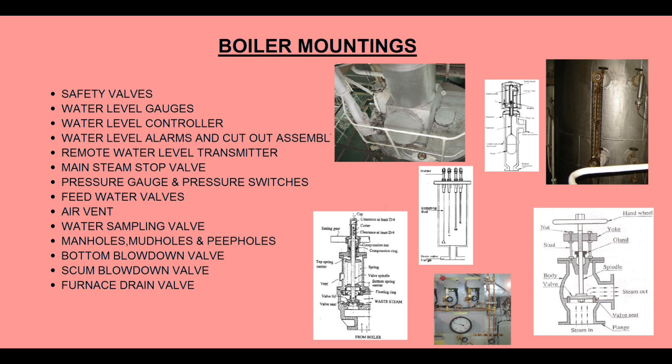Scum valves are fitted to the steam drum and connected with a shallow dish positioned internally at the normal water level. This is to remove oil or scum from the surface of the water. Air vents are fitted to the highest point of the boiler drum in order to release air when filling the boiler, when initially raising steam, or to prevent forming a vacuum when totally depressurizing the boiler. Pressure gauges and other instrument connections are fitted as required to the steam drum and superheater outlet header to provide the necessary pressure readings.